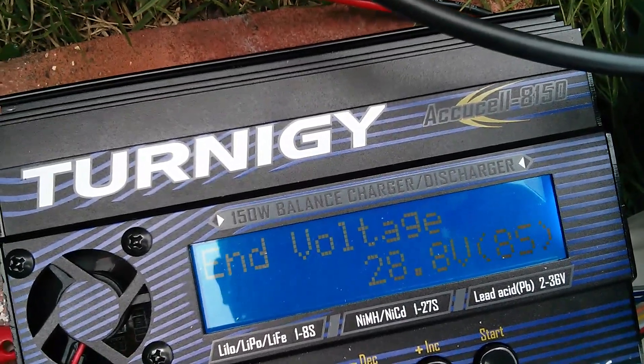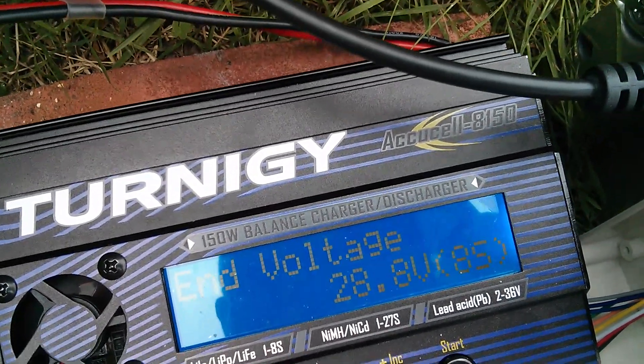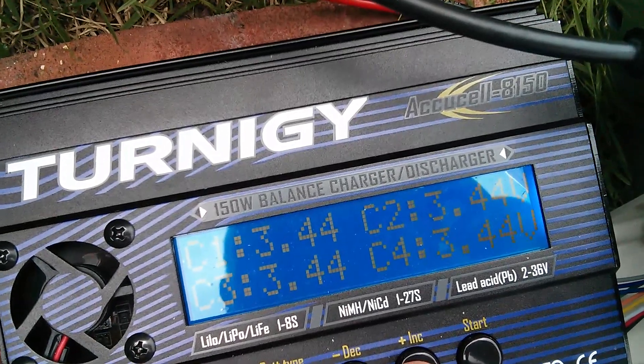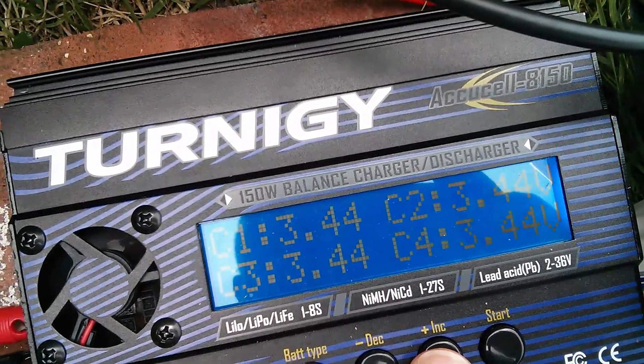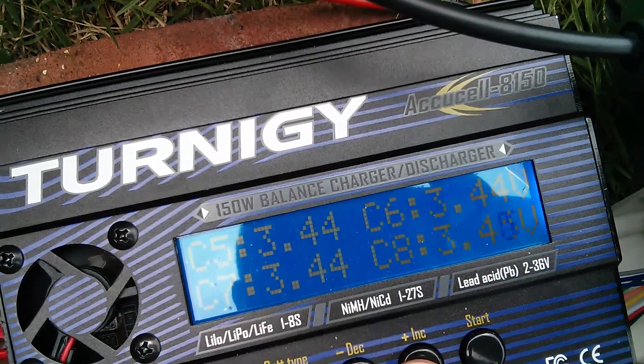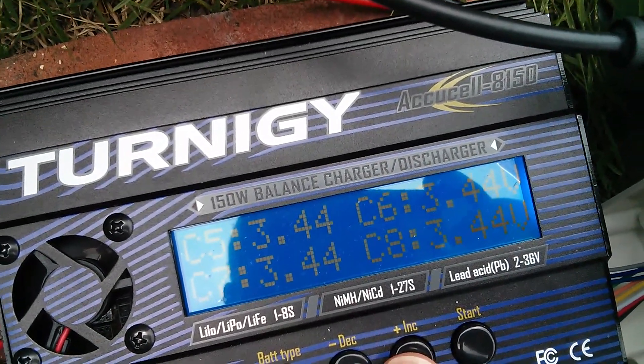3 amps, at 28 volts. That's going to go to 28.8. I can show that by pressing the Dec button to show the end voltage — 28.8. Now if I show the cell voltages, they're all beautifully in balance. 3.44 for the first four cells, 3.44 across the board for the second four. So it's all good.